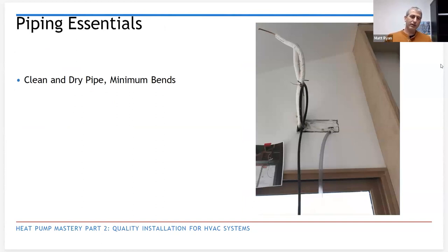Making sure piping is kept dry and clean, taping the ends, making sure it's sealed off and not just left wide open. This picture here I took as an example: we ran the line set at rough-in, so we boxed out a little area. So we had some room to maneuver and work at finish when that cassette actually got set. Just good practices.